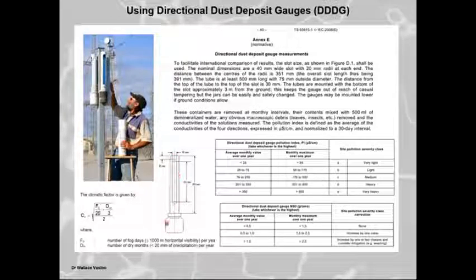And then what we do is we add distilled water, measure the conductivity of the water, and from there we determine what the pollution level is. And here you can see we have different values which we can then associate with different pollution levels. We correct for our fog days and dry months with the climatic factors. So if you've got more than 20 fog days and more than 3 dry months, you're going to find that you have to do a big correction. And then we also look at the non-soluble components, the stuff that does not necessarily conduct but adds to the thickness of the layer, and we also correct for that.